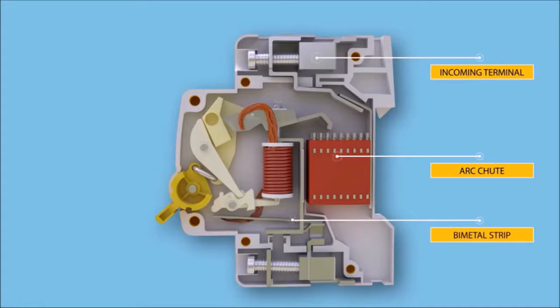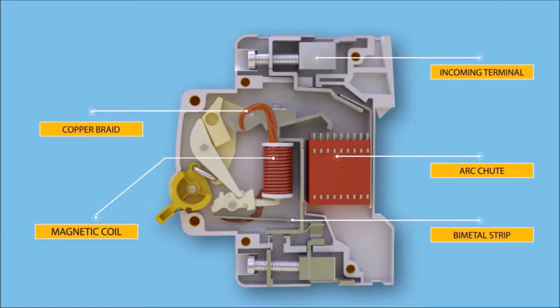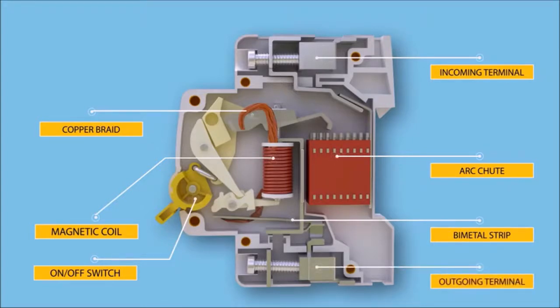Bimetallic strip is part of thermal tripping arrangement, around which a heater coil is wound to create heat depending on the flow of current. Magnetic coil is part of magnetic tripping arrangement, where in case of short circuit or heavy overloads, a strong magnetic field is produced in the coils. Copper braid connects the moving element with the static element. On-off switch is the operator with which we manually interrupt or turn on the electric circuit. In outgoing terminal we connect the outgoing phase from the circuit breaker.